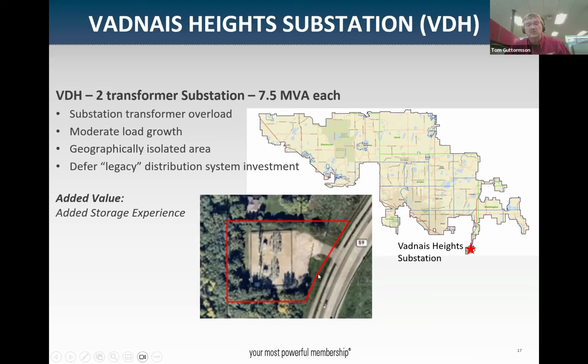If one of these transformers fails, we have to pick up the load from the other, and there are parts of the year where it's very difficult to do that. We don't want to be in a situation where if we have an outage, we cannot turn the lights back on - that's not acceptable. The area here is fairly well developed, so there's not a lot of growth, but native growth is enough that under these backfeed scenarios, the transformers could be overloaded and we'd need a substation project. But upgrading it to meet that deficit would be a major project and an overkill of capacity.